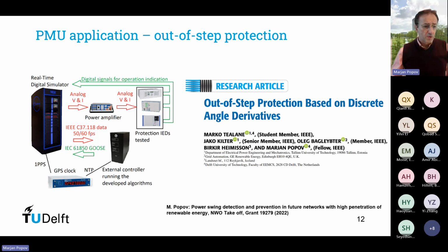The system has been simulated in the RTDS environment, and normally we used virtual synchrophasors by making use of the GTNet card to transfer synchrophasor data according to the IEEE standard 37.118 to the phasor controller. And upon occurrence of a particular disturbance, whenever the protection was supposed to operate, the tripping command was sent back to RTDS by using GOOSE messaging.